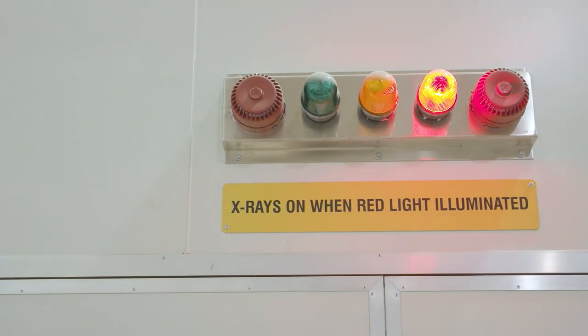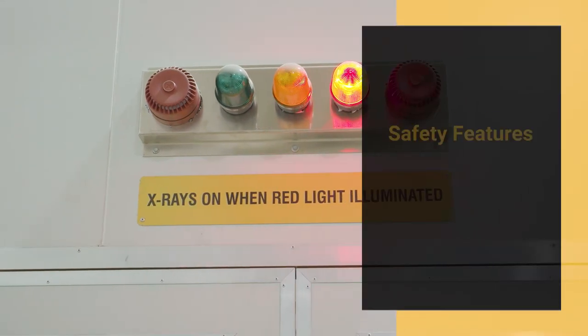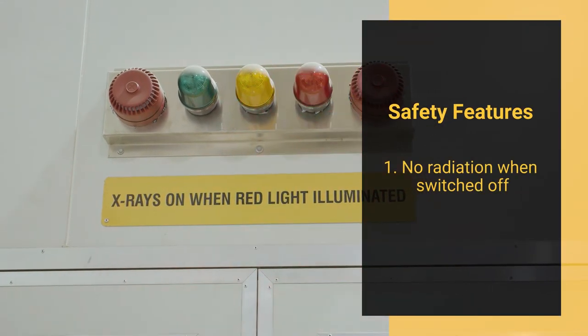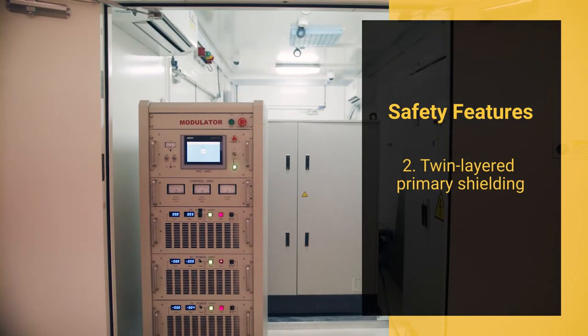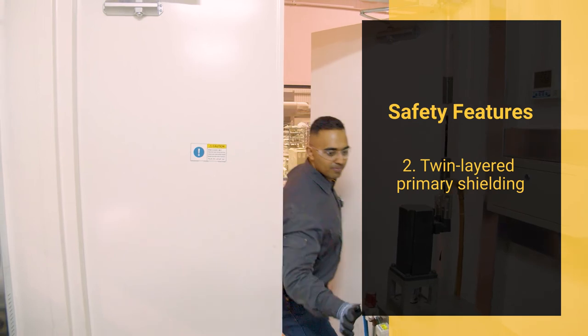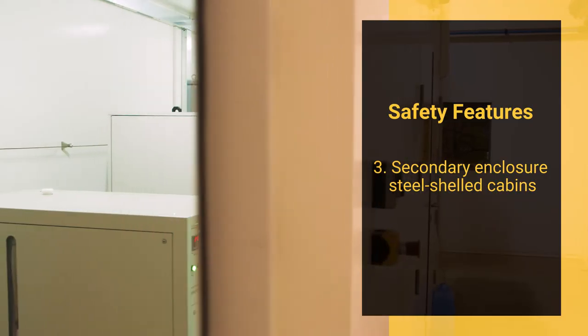The photon assay unit includes a high-energy linear accelerator X-ray source that produces no radiation when not powered on. However, to ensure safe operation, the unit includes a suite of features designed to prevent both long-term and accidental short-term exposure.